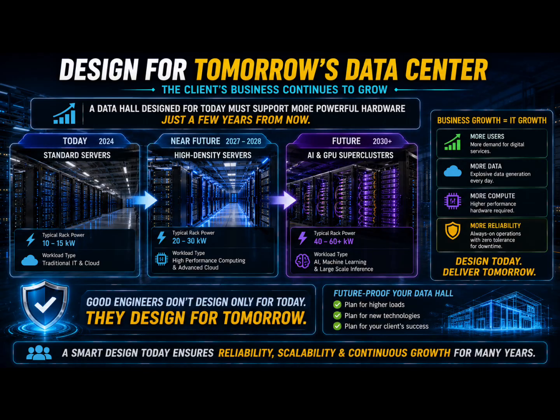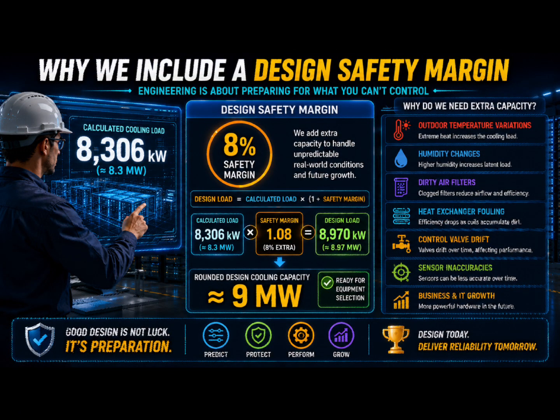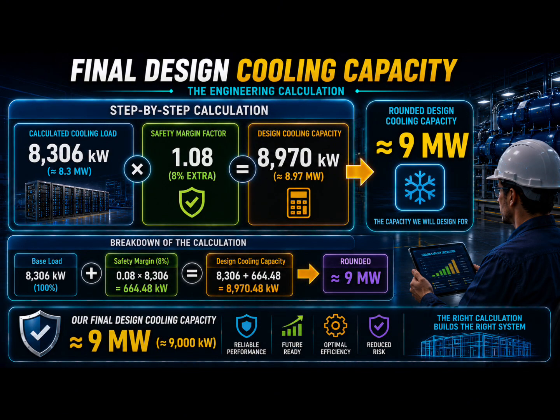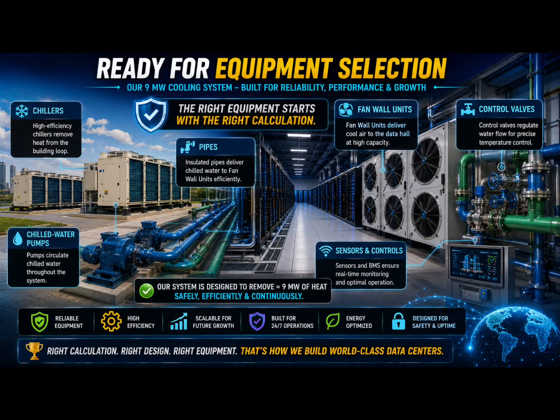They design for tomorrow. That's why we include a design safety margin. For this project, we'll use 8%. Let's calculate it. 8,306 multiplied by 1.08 equals 8,970 kilowatts. Rounded, our design cooling capacity becomes 9 megawatts. Now, and only now, are we ready to select our cooling equipment.